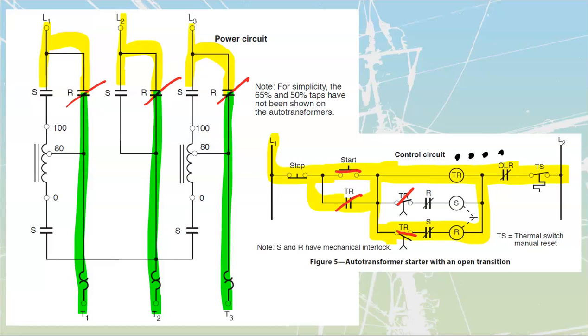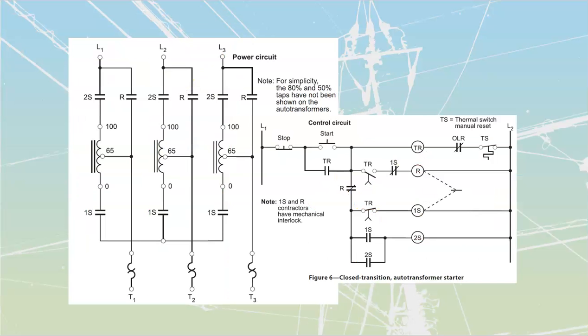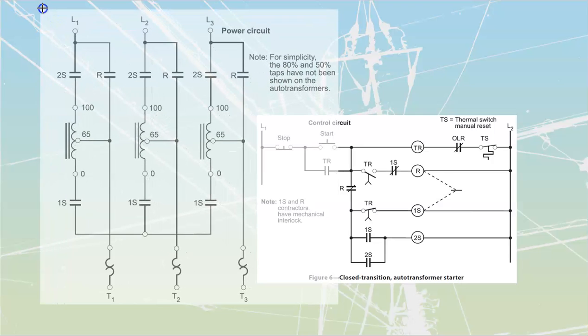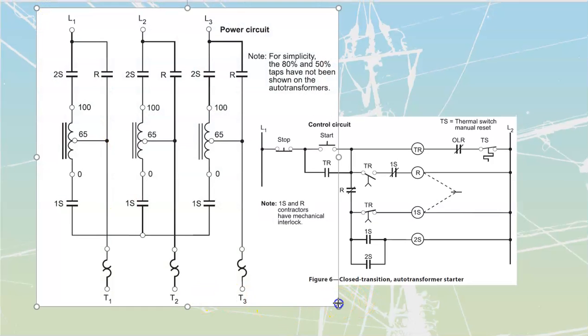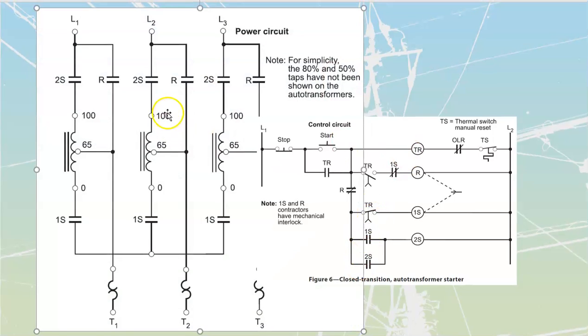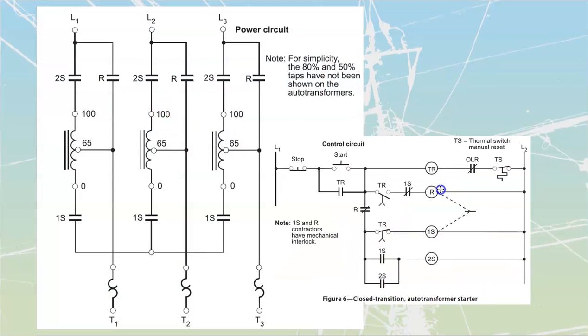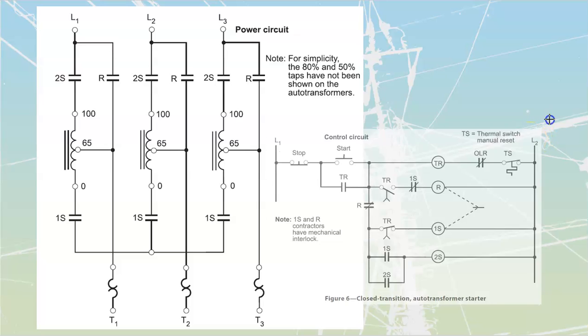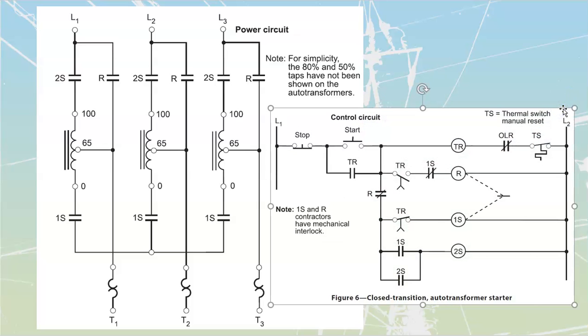Okay, let's take a look at the next one, which is going to be my closed transition autotransformer starter. All right, so this is looking at the autotransformer starter, the Y, and this is going to be a closed transition one, which means we're never going to see a drop in the amount of torque that we're going to be delivering out to our loads, which is a very good thing once again. And we are also going to see a more balanced amount of current that we are going to take out. As a result, we're also going to have a more balanced value of voltage that we are going to get off of these two.